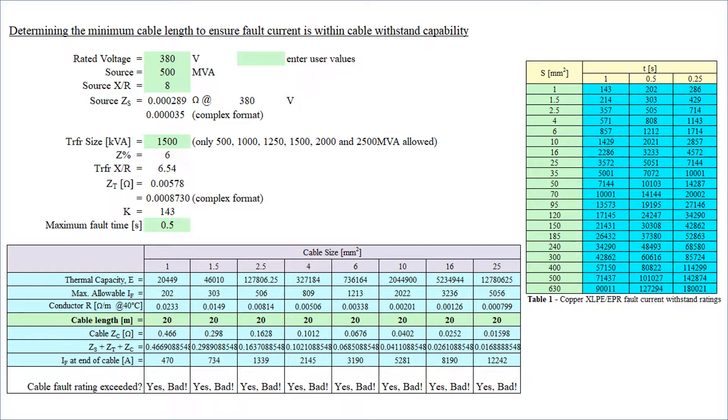Let's work through this. My voltage as I've said before is 380 volts, source is 500 MVA, X/R is 8, and from this I can get my complex source impedance. Note complex algebra is required as our impedances are complex quantities R + jX. Transformer size is 1.5 MVA, impedance is 6%, X/R is 6, and so I can calculate my transformer impedance in complex format as well. K I got from tables is 143, and my maximum fault time is 0.5 seconds.